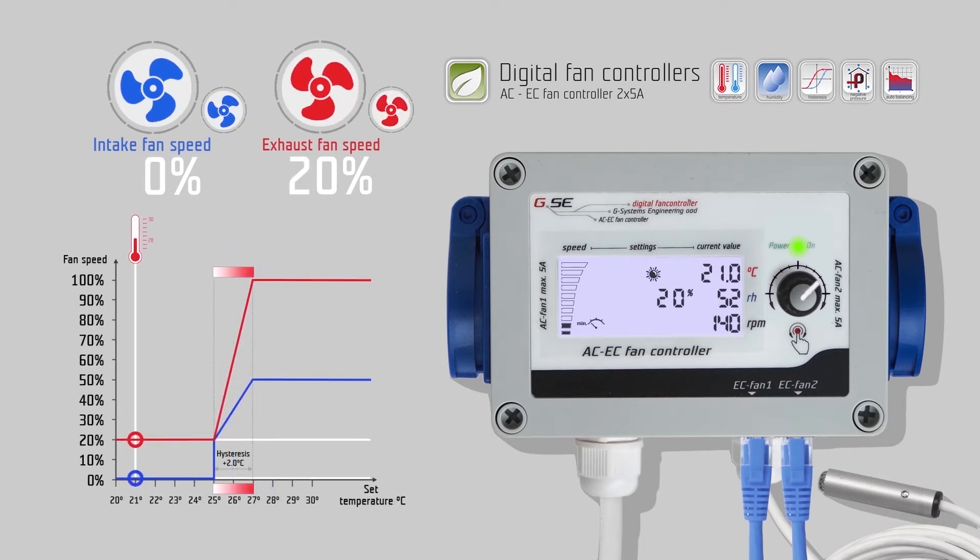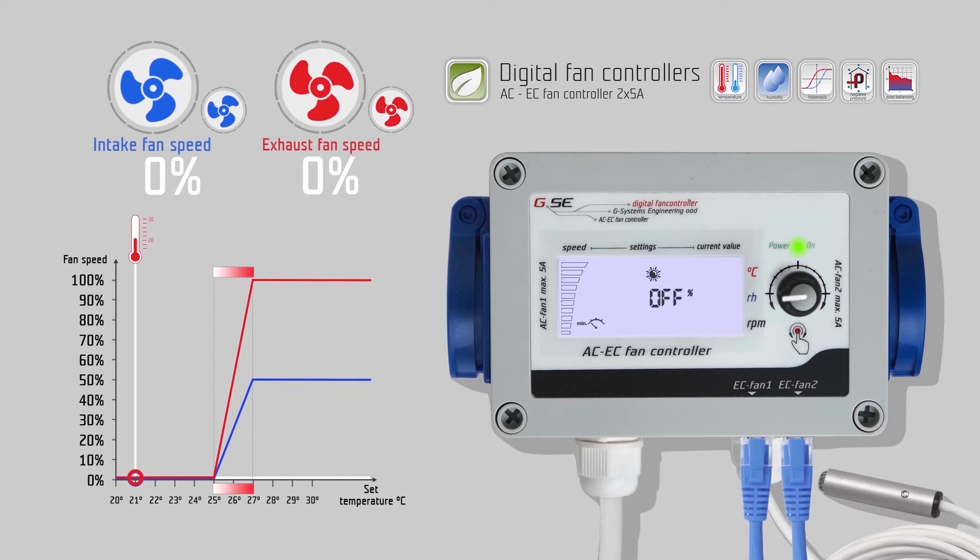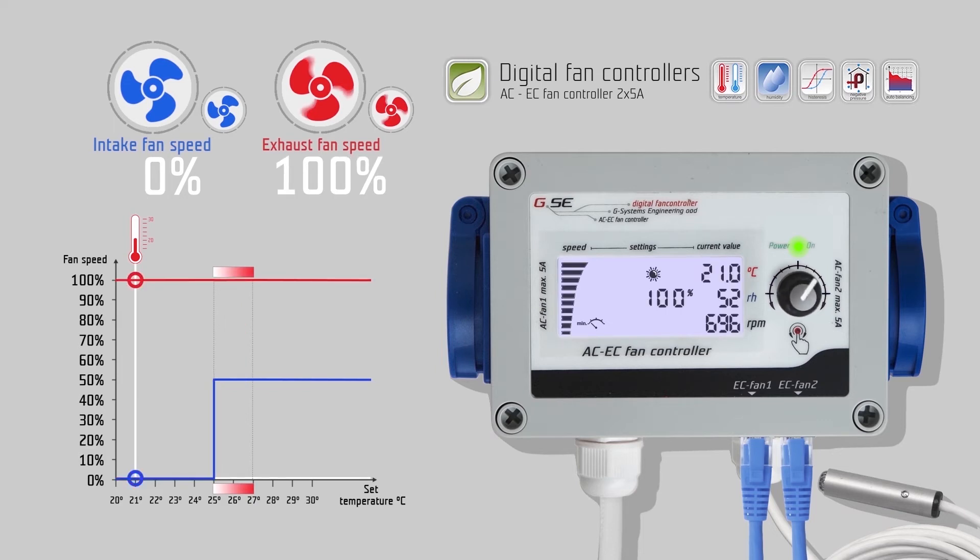Turn right to go to the minimum speed dial setting. The minimum speed setting limits the exhaust fan; it should never be undercut during the regulation. The current minimum speed is displayed on the bottom side of the speed bar. Each filled segment represents 10% fan speed. If the value is set to 0%, the exhaust fan will stop working when the measured temperature or humidity are below their set values. The minimum speed can be set up to 100% speed. For example, we set the value to 10%.